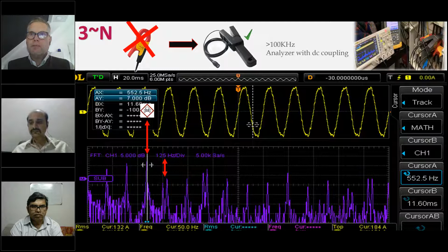You see, and you look at the signal, you see all these spikes, it's not a neat voltage anymore. When you look at the power quality analyzer from Fluke, which has low resolution current clamps, you will not see, you cannot look into the sinus. That's interesting about high frequency current clamps, which can also measure direct current. Of course, with just a coil without a Hall generator, you cannot measure direct current.